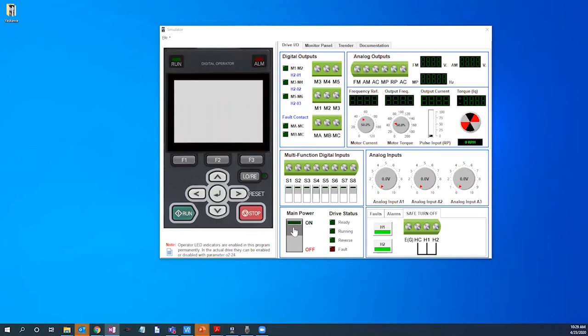Coupled with this flexibility in voltage and horsepower is a full range of control methods including volts per hertz, closed loop volts per hertz, open and closed loop vector control, as well as advanced open loop vector. Today we will perform a basic startup with the volts per hertz control method.